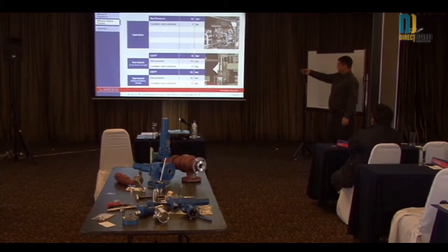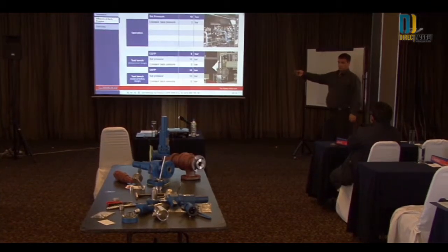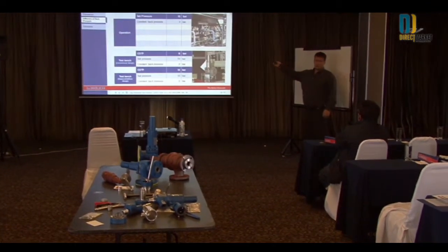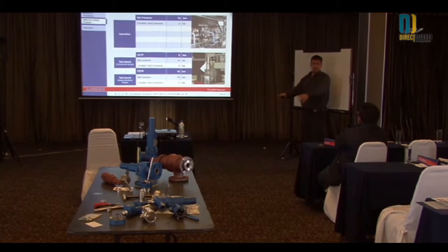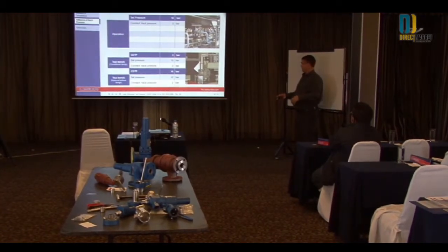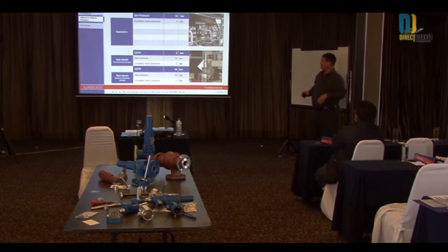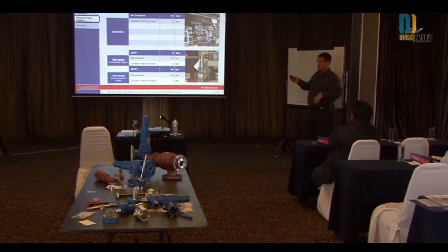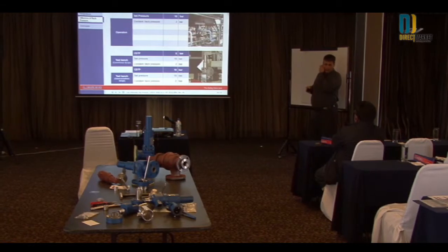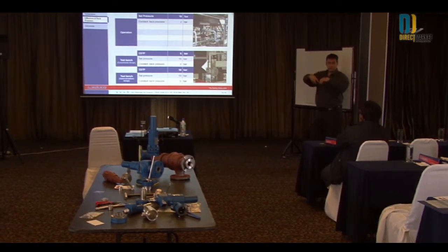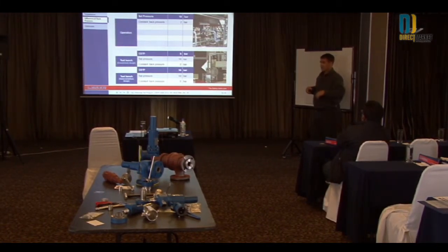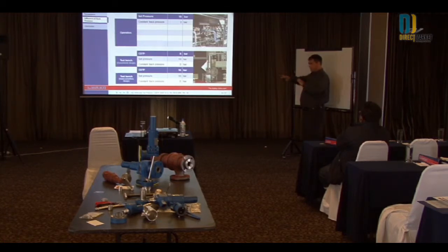So if you were to put a balanced bellows in the situation, you wouldn't have to compensate for the back pressure. You would set it on your test bench in your facility or your maintenance facility at 10 bar. You kind of see how that works? If you had a conventional valve without a bellows, you'd have to set the valve a little bit lower to compensate for all those forces pushing on the disc. And with a bellows, you don't have to worry about it.